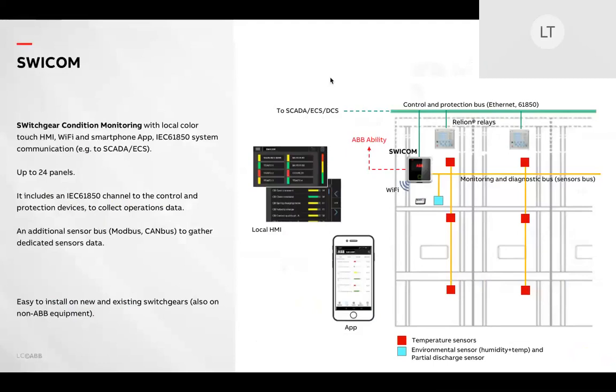The overview image that you see on the right side of the page shows SWICOM connected to the relays on an IEC 61850 backbone. SWICOM connects both temperature and partial discharge sensors. SWICOM is then connected to the site SCADA, electrical control system, or digital control system, and or Ability Cloud via a dedicated gateway. On-site solutions via HMI and handheld devices are available. The handheld device connects via the SWICOM QR code and will automatically disconnect after a period of 1 minute of inactivity. So once connected, it does not always stay connected. You leave the switch room and you lose the connection.